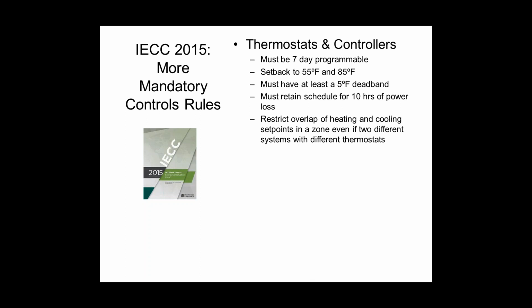But if you do that, you have to have something that interlocks these things, so at no point in time can the heat come on with the cooling. It can't be, oh, I told the building operator to never let them overlap. That's not good enough. It has to automatically prevent them from overlapping the heating and cooling set points so you can't simultaneously heat and cool.